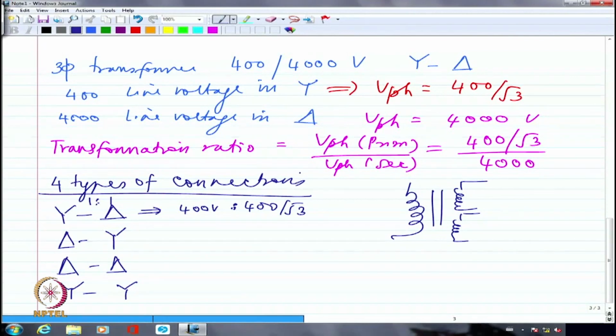So 400 divided by root 3 will appear as the line voltage on the delta side. So it's 400 volts is to 400 by root 3. This actually creates an automatic step down. Whether I like it or not, star delta configuration generally steps down the voltage on the delta side compared to the star side, even with 1:1 transformation ratio, because it's a phase-to-phase transformation ratio, and in delta the line voltage and phase voltage are equal to each other. So essentially this is a step down configuration.